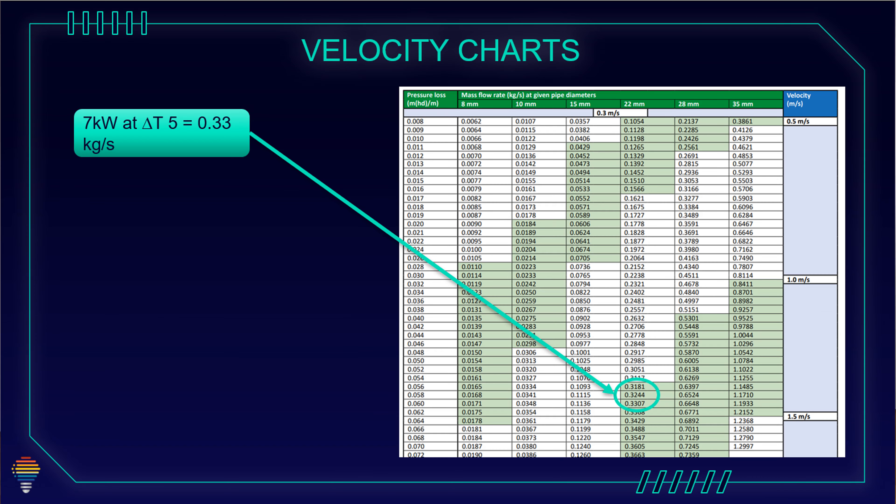Also, what is important, it is important to know that this is primary pipe sizing because this is from our heat source to whole emitters. If we have a few different sides or a few different pipe works in our house, we need to go with the same heat required for these diameters. For example, if we have 7 kilowatt unit from table, we need to go with copper pipe of 22 millimeters.